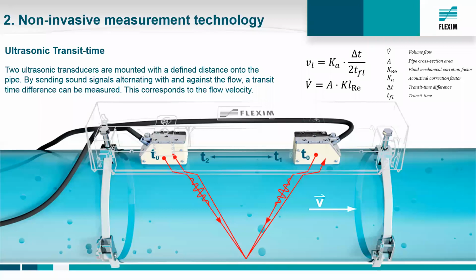What does it mean? It means that each material which is in action here, like the wedge material, the pipe material, and also the fluid, has its own specific sound speed. According to these sound speeds on the transition phases, the ultrasonic signal is refracted at a certain angle. And this is considered in the volume flow calculation. Please remember this. We will come to this later when we look at the challenges. To include the flow profile of different fluids into the calculation, the fluid mechanical calibration factor K Reynolds is added. Today we are focused on water mains, so the media is set as water.